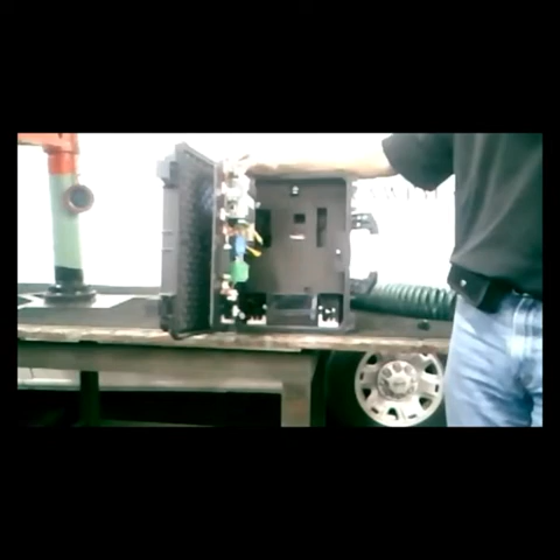All of our devices, you can pop a micro SD card here on the PLC, and we have adapters to slide into your computer's USB, and you can drop that data into your GIS program and map all the flushings the crew did by hydrant. Every time they do a flush, over time you'll see a history of the flush from this particular data that's dumped in there.